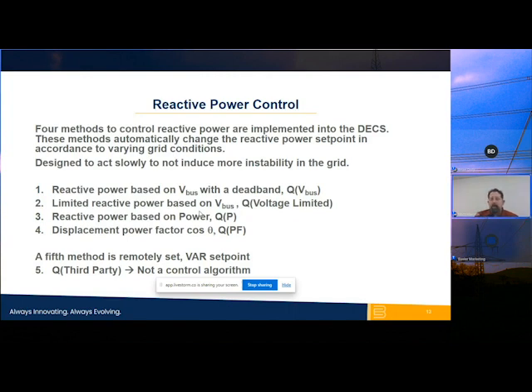Method number 1 is reactive power based on the bus voltage or the grid voltage with a deadband. What this means is we're going to set a slope, and we can define that slope. As the bus voltage fluctuates, we are going to change the reactive component, or the amount of reactive power, in and out of our grid connection based upon that voltage fluctuation. So it's a direct relationship between the fluctuations of the bus voltage and the excitation, the amount of control and the amount of VARs, or kVARs, that will be exported from that particular machine. And then we add a deadband because, again, we're looking for a slow response. There is a deadband that can be defined based upon our settings. We call that QV bus.